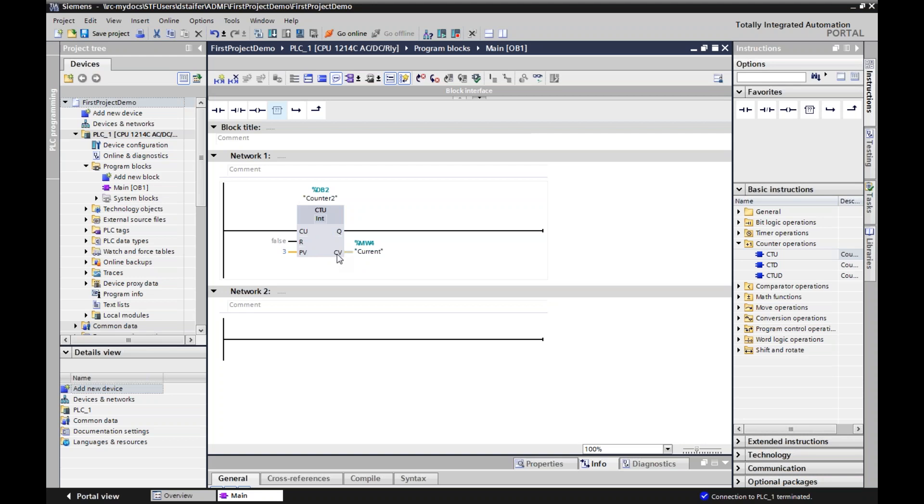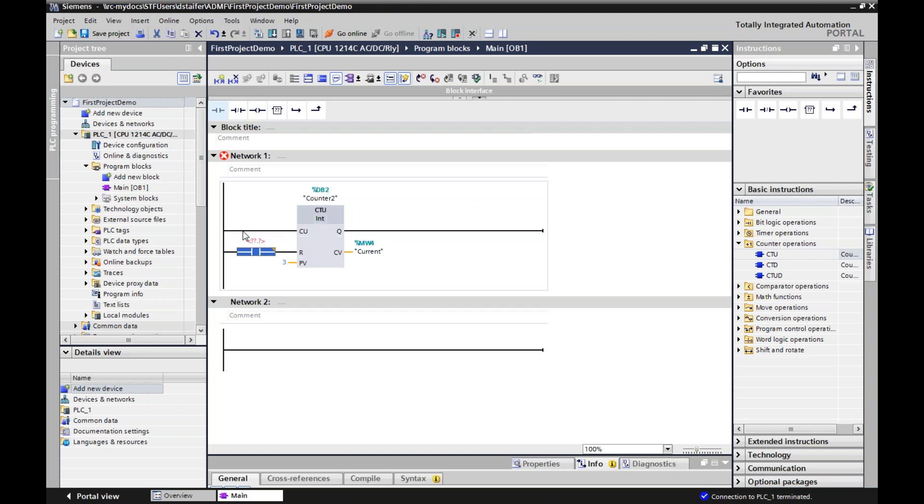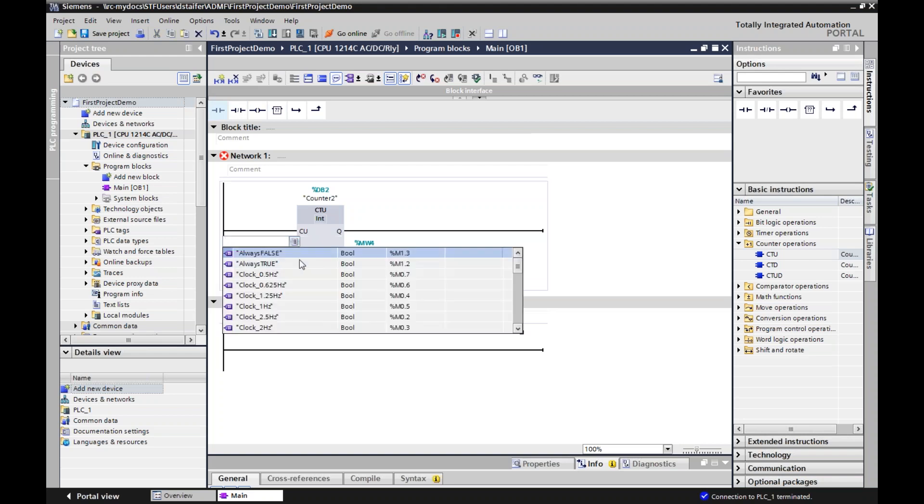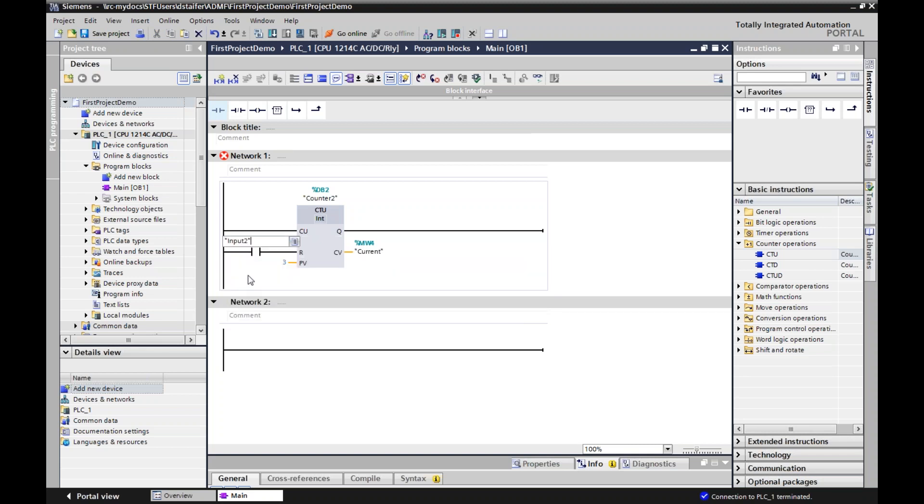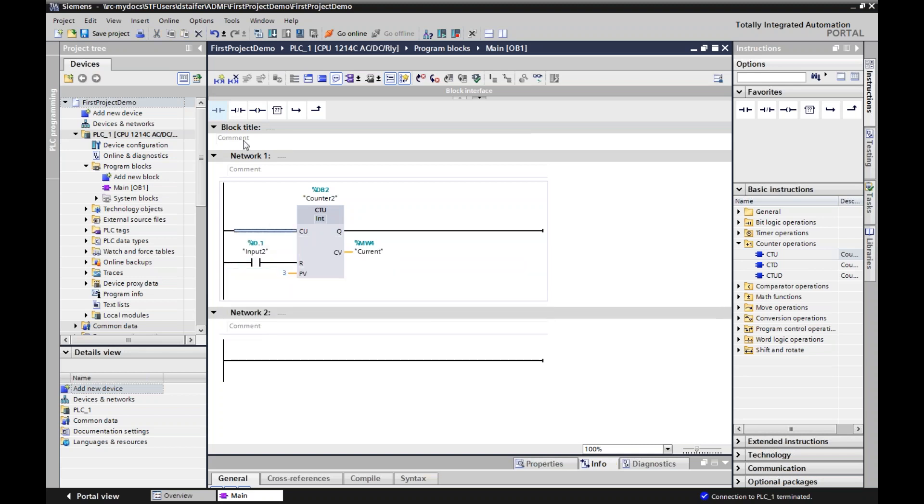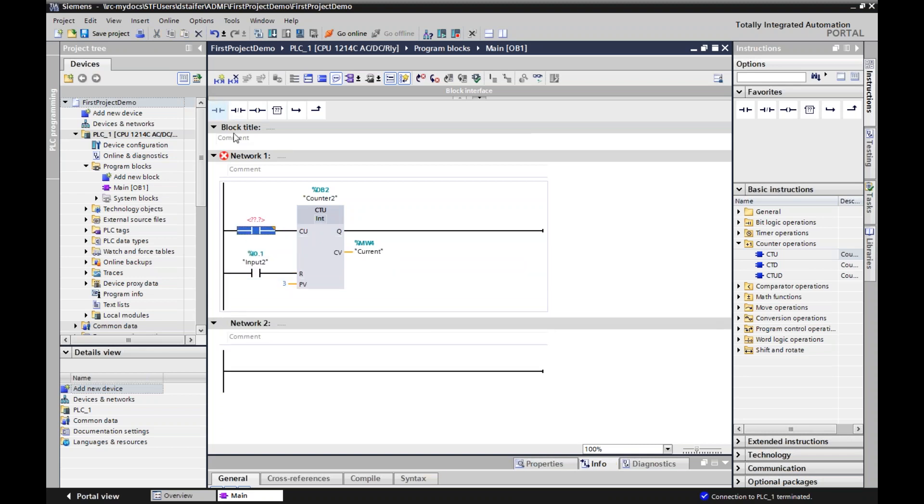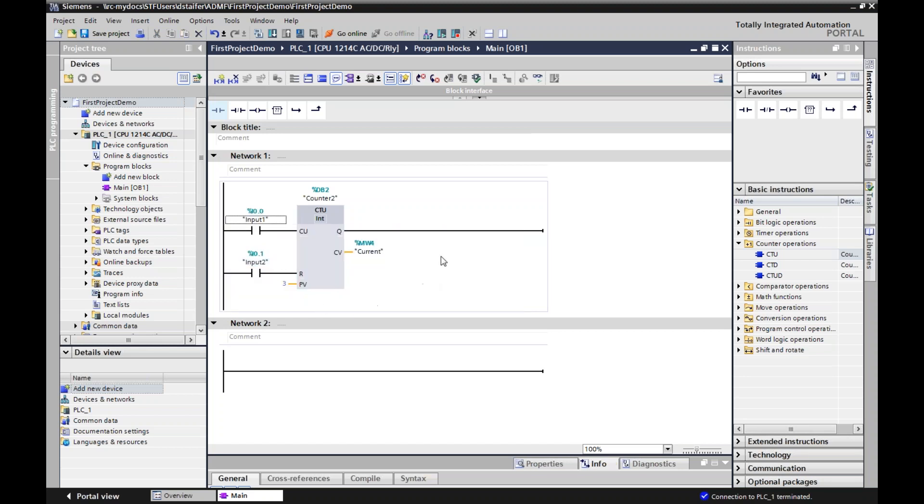Now when we have three dots here, we don't have to put anything here. But again, we can put a memory word in here and whatever the current value is of this counter, it will be put in this memory word. So this has some functionality. You don't have to put anything in this current value, but if you want to use it in another program or an HMI, you will need to put a memory word.